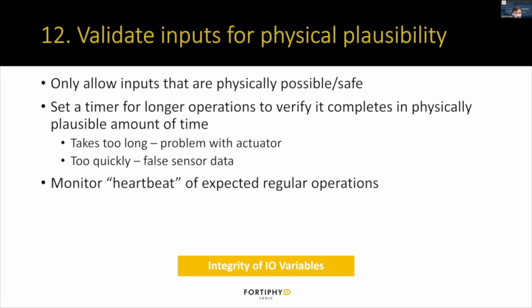There are different variations on this. You can also add a timer for longer operations to verify that it does complete in some physically plausible amount of time. So maybe you have a big valve that takes a few seconds to fully open or close. You can actually time that operation and detect that if it took too long, maybe it's stuck, or maybe something's not working right. Or if it happened too quickly, either that's false sensor data, maybe some wiring is wrong, or an attacker is injecting false data to say that it did successfully close or open when it did not.